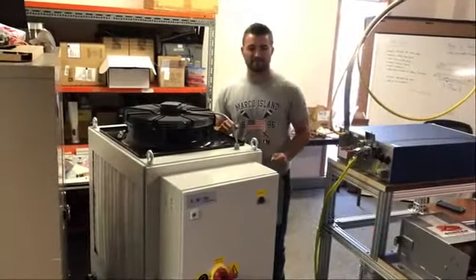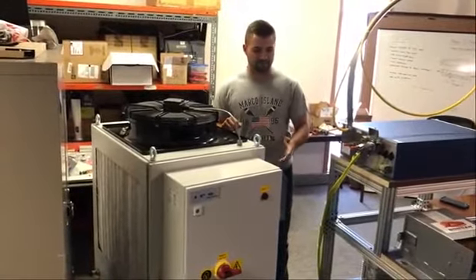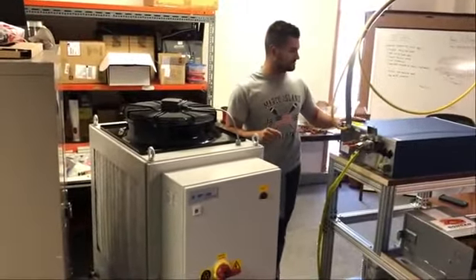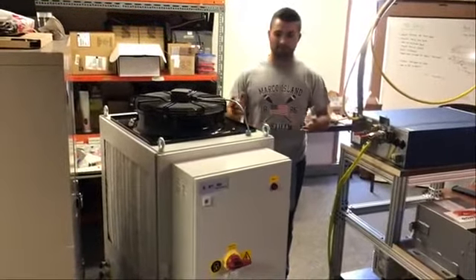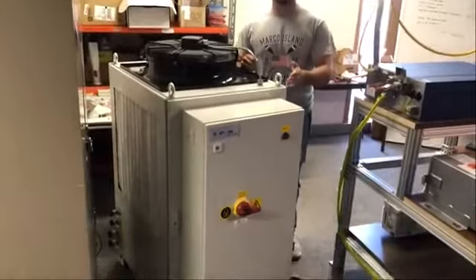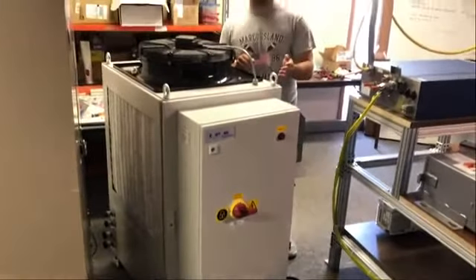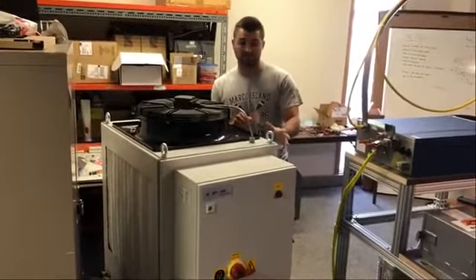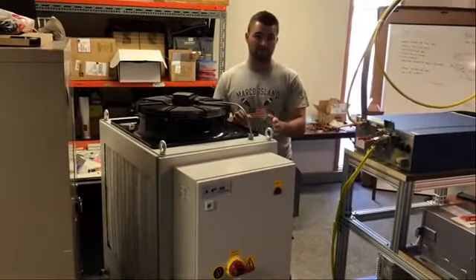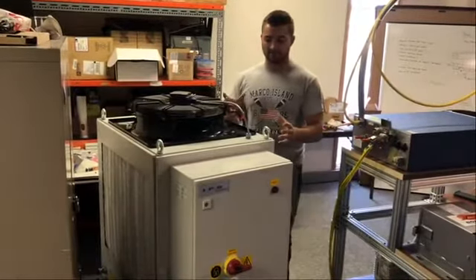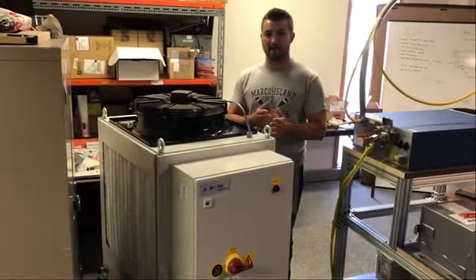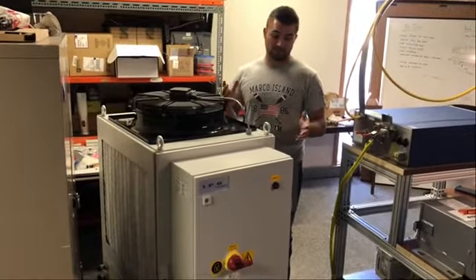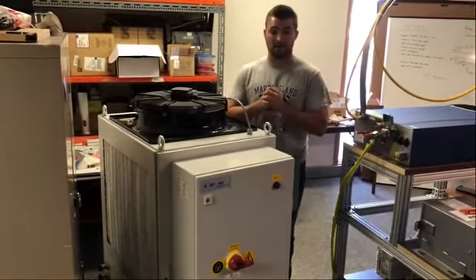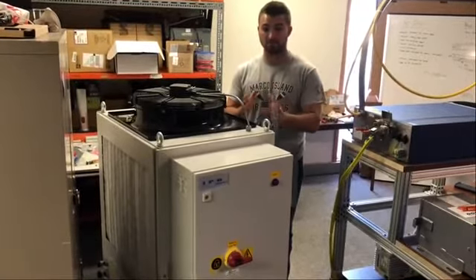This here is the IPG Photonics chiller. Its main purpose is to cool the laser generator and the wobble head to keep them from overheating. It uses deionized water, and it maintains the fluid inside between 21 and 25 degrees Celsius. The pressure it supplies is 1.5 to 3 bar, and it supplies up to 10 liters of water per minute, so it's a pretty good cooling system.